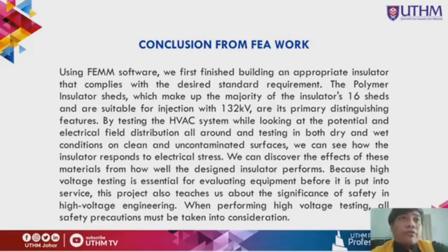Using FEMM software, we first finished building an appropriate insulator that complies with the desired standard requirements. The polymer insulator with 16 sheds makes up the majority of the insulator, and being suitable for injection with 132 kV are its primary distinguishing features.